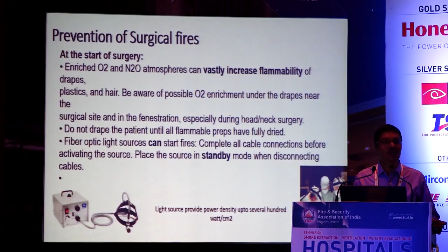Fiber optic light source. Earlier I was also wondering how the fiber optic light source can contribute, because some of the things we have not tested because we cannot afford to test them. But luckily some institutes like ECRI send videos on what has happened, and they have simulation conditions. So a fiber optic light source can start a fire. It has a 300 watt xenon light source with a fiber optic cable of 1 meter. If the machine is not in standby mode and you take the cable out in an oxygen enriched environment, it may lead to a fire.